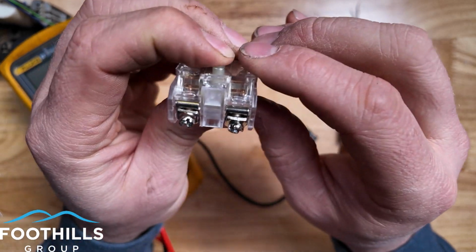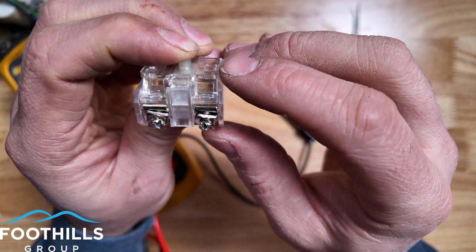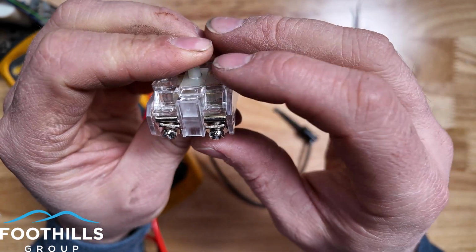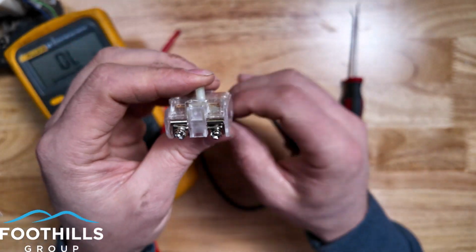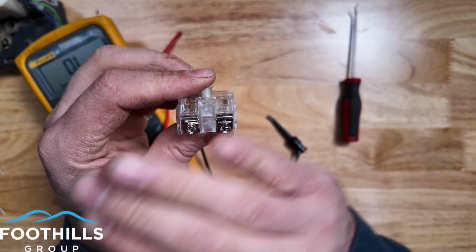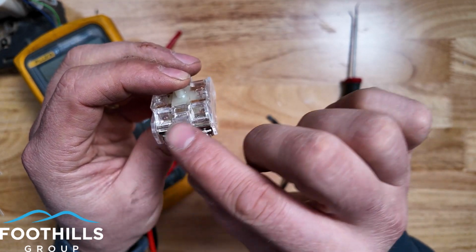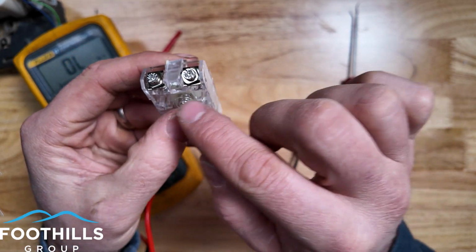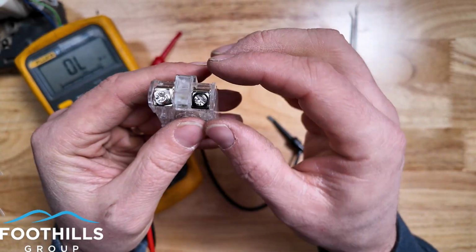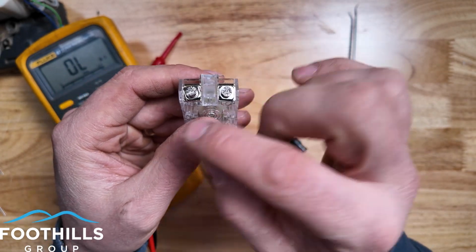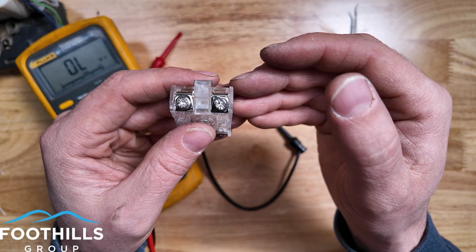And if we don't, if we have a high resistance, really this should be very close to zero, almost on zero, so 0.1, because my meter's base resistance is 0.1 on my leads right now. So a 0.1 reading, that's good. But if we consistently got 8 ohms here, that 8 ohms would be creating an unwanted resistance in this switch, which will create a voltage drop. And in our electrical circuits, any voltage drop in a circuit is a loss unless it's our desired load.